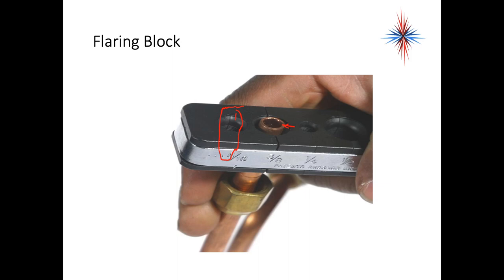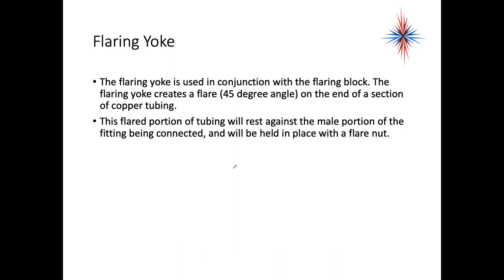The width of a quarter or nickel is a good measurement of how far that sticks out. Don't forget to put the flare nut on before you put this into the flare block. Once you flare that pipe, you can no longer get the flare nut on it. The flaring yoke is used in conjunction with the flare block.